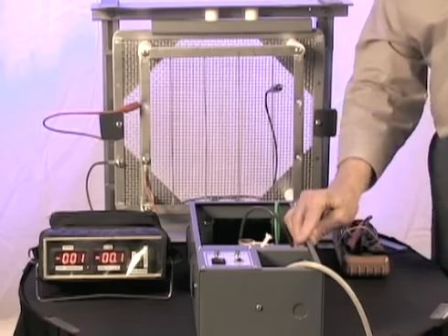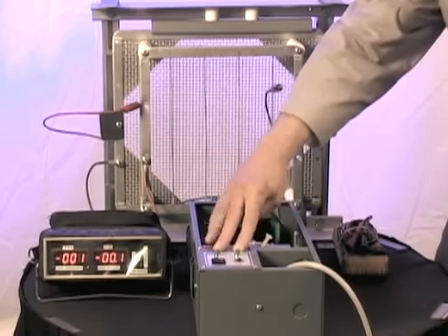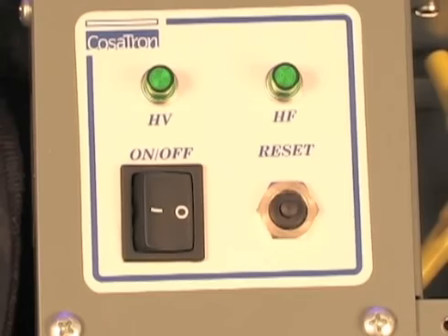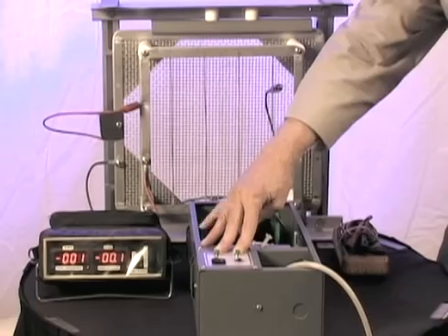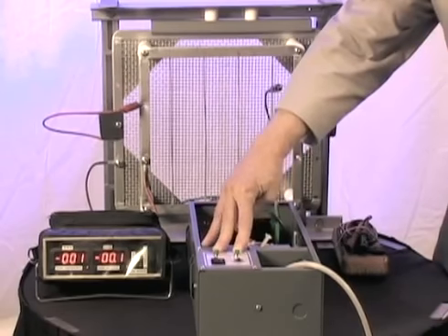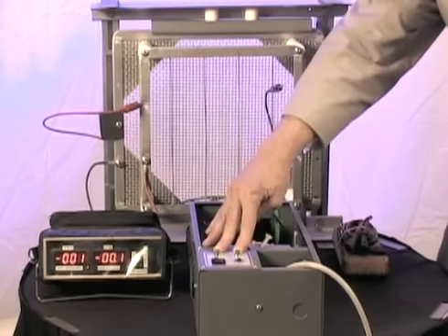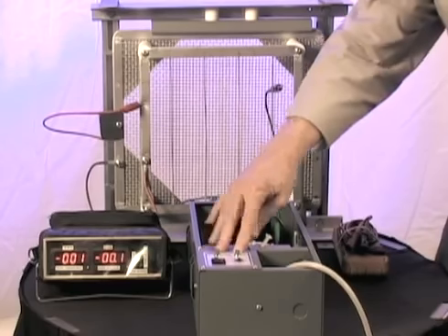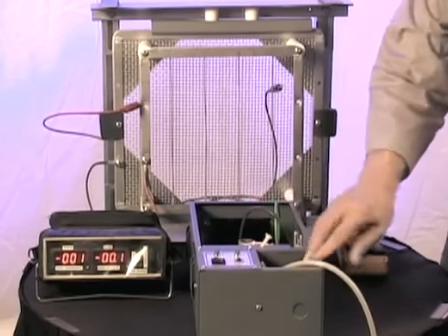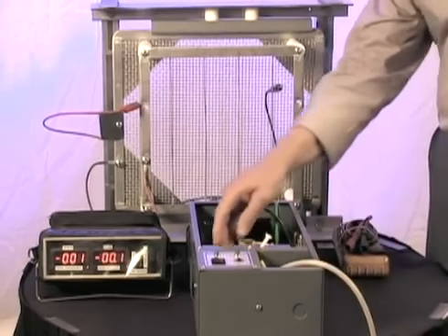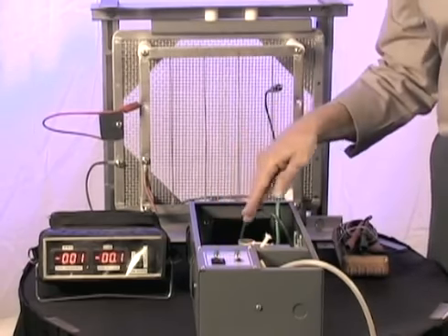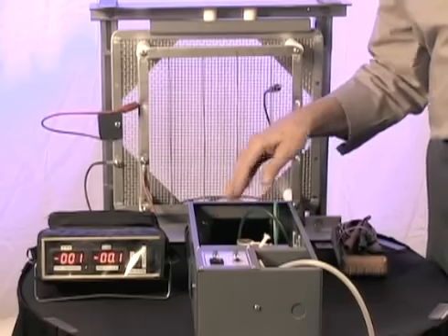When you first start to do this, if you approach the generator and both lights are off, the first thing to do is to check to see if you have incoming power rated at what the generator is supposed to be hooked up to. It can be anywhere from 100 to 240 volts on the incoming power. All power after that through the transformer internally will be 110 going to all the other circuits.